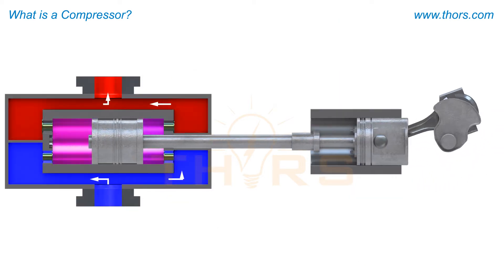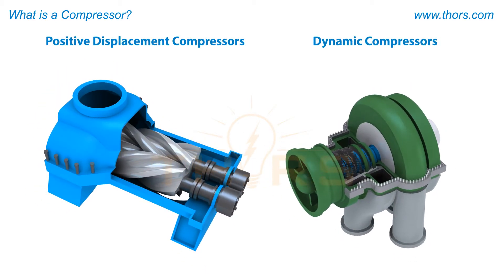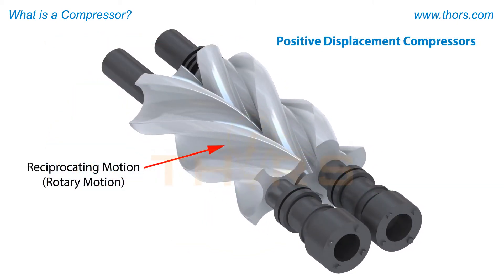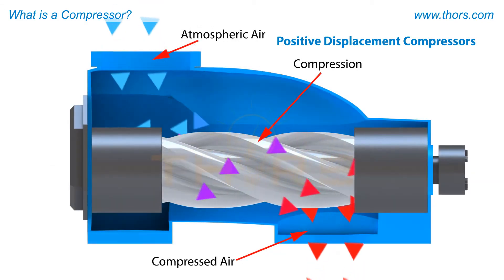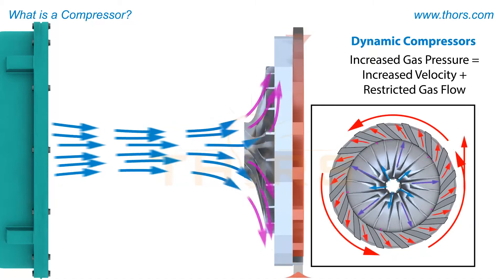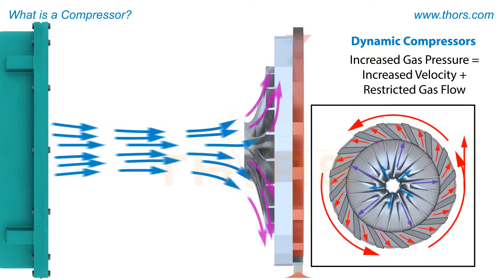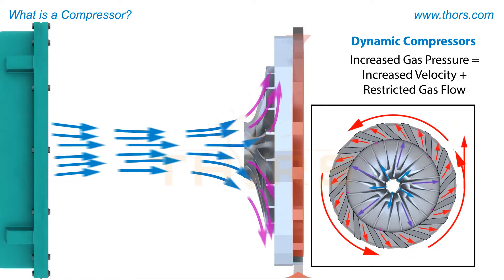More advanced compressors operate in a similar fashion. The various types of compressors can be classified as either positive displacement compressors or dynamic compressors. Positive displacement compressors will either use reciprocating motion or rotary motion to produce compressed air. Dynamic compression increases gas pressure by increasing the velocity of a gas and then restricting the gas flow by passing it through a diffuser. Reducing a gas's velocity causes the gas's pressure to increase.